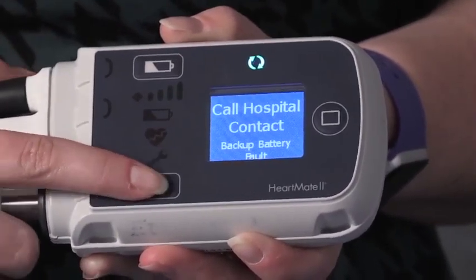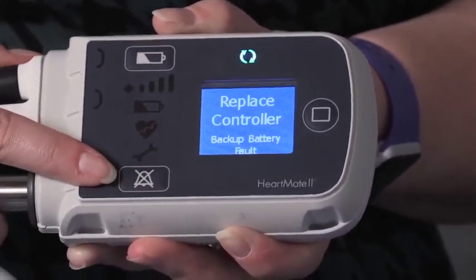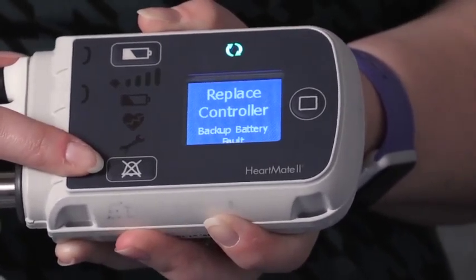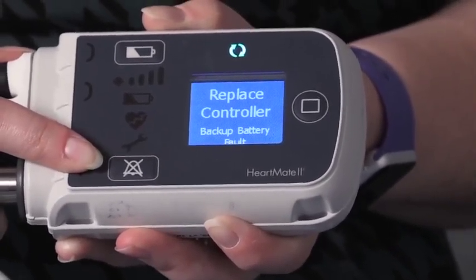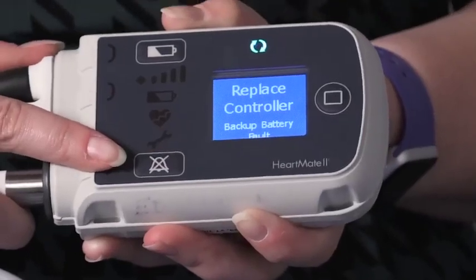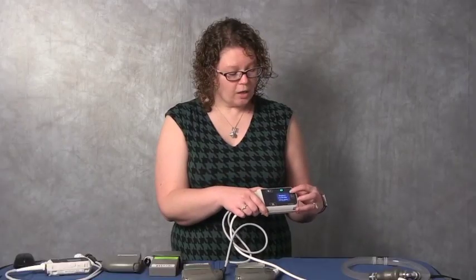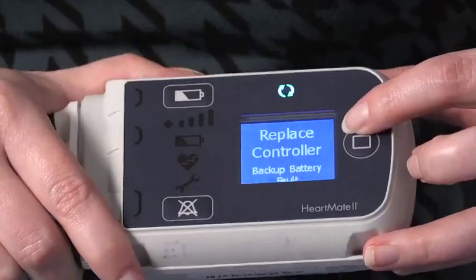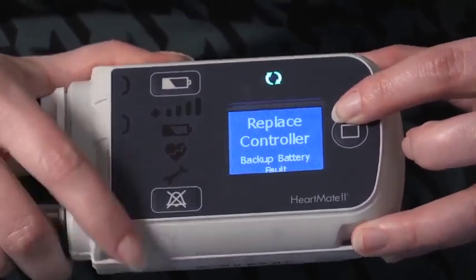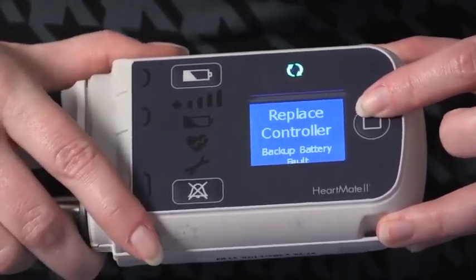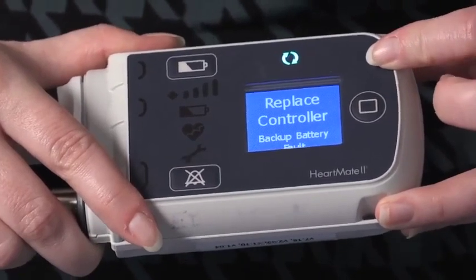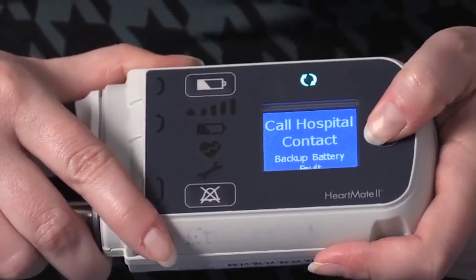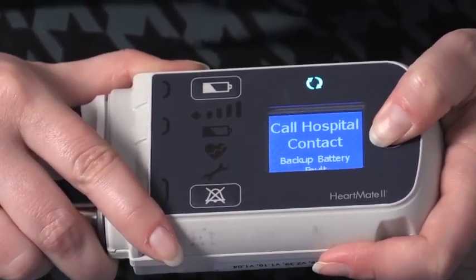Our silence button works to silence the alarms. It doesn't fix any alarm condition, but it just makes everything be quiet so that we can talk on the phone, hear each other, and troubleshoot appropriately. Our screen here is your display. As you can see, it's displaying the error message related to this yellow wrench alarm, backup battery fault. The other thing that we can do with this square button over here is scroll through our VAD numbers.